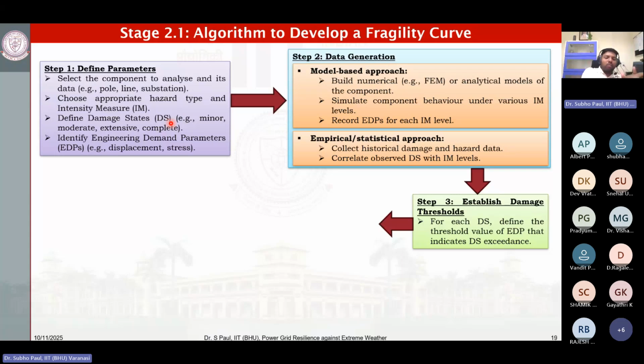That failure probability you plot or fit to a particular probability distribution function - PDF or cumulative distribution function, CDF. If it fits with, let's say, 90% or 95% accuracy, then we can say we got our fragility curve for a particular equipment. For the fragility curve, we keep the x-axis as the intensity level, and the y-axis as the probability of failure, and we save that for the resiliency analysis of the power system.